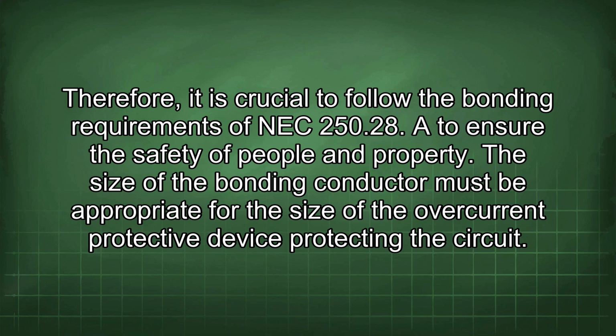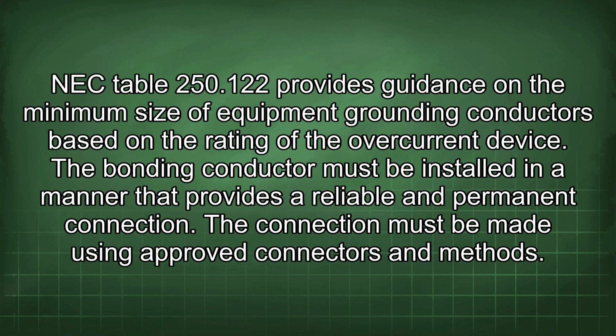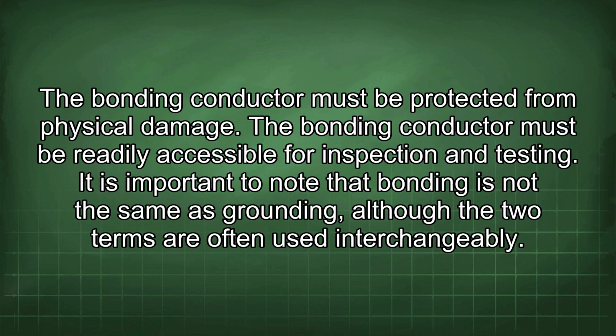people and property. The size of the bonding conductor must be appropriate for the size of the overcurrent protective device protecting the circuit. NEC Table 250.122 provides guidance on the minimum size of equipment grounding conductors based on the rating of the overcurrent device. The bonding conductor must be installed in a manner that provides a reliable and permanent connection. The connection must be made using approved connectors and methods. The bonding conductor must be protected from physical damage. The bonding conductor must be readily accessible for inspection and testing.